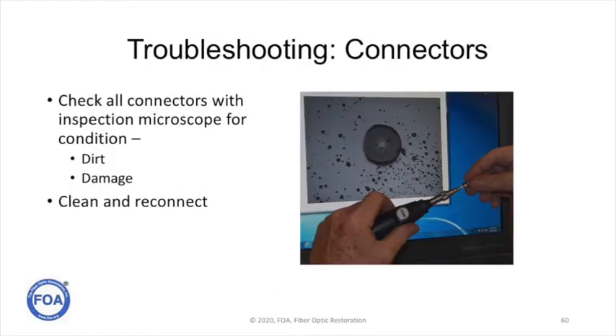Everybody in the communications electronics business will tell you that most of the problems are associated with connectors. So the first thing you always do when troubleshooting is check the connectors. You disconnect them, take a microscope, look for dirt and damage, clean them and reconnect them. That's where you start with all the troubleshooting of the cable plant.